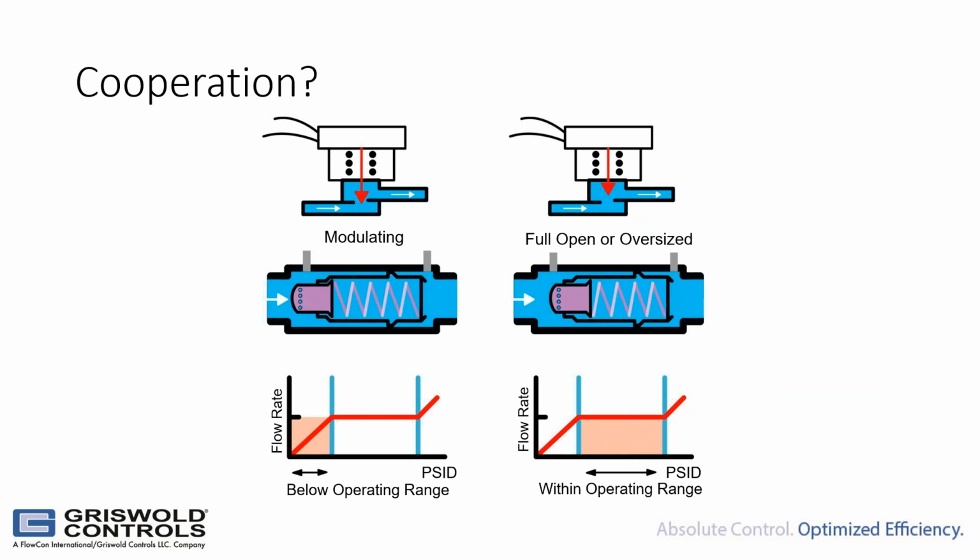This makes sense from an authority standpoint because for those of you that size control valves, you know that whoever's controlling the flow is the one that has the most pressure drop. So here, this flow limiting valve is about 1 pound, and the modulating valve by design should be 3 to 5 for modulating. And that pressure differential is actually going to be higher as that valve closes. So it's 3 to 5 at 10 GPM, but as it drops to 6 GPM and 5 GPM, it'll have 10 PSI across it, 12.